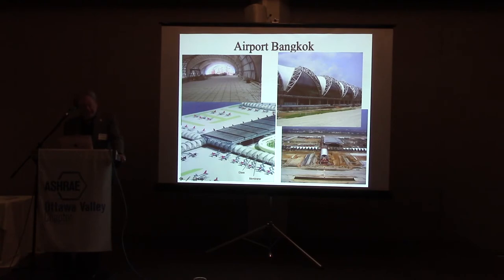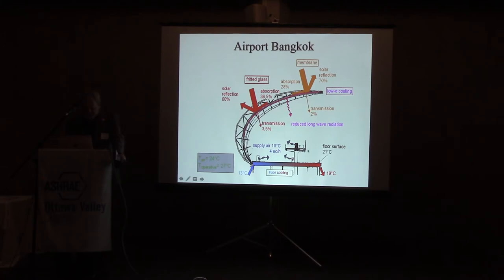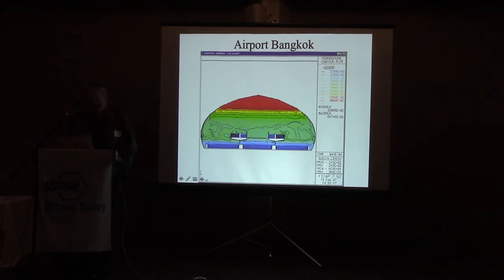So you can imagine in Bangkok, where it gets over 40 degrees very often, and you have a lot of sunshine, that the load in the concourses was very high. And to use a full air system would cost a lot of energy. So the design was to integrate piping in the floor. You may not be able to see it, but here the piping is put in all the floors in the concourses. And it's combined, the floor cooling, see here, with a displacement ventilation, so we get a stratification in the space. This was tested by CFD calculation to get this stratification.